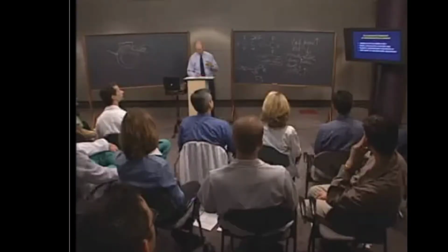In Grand Rounds this year, we had a discussion on pouring water into the absorber, and our institution said not to do that. If you had any concern about it, take off the lower canister, if not both, and replace it with fresh. Does the insert on the absorber say that you can pour water into it? I don't know. But I know you can. And I know that there's been at least one study that suggests that it works, that you will rehydrate the absorbent simply by pouring water into it.